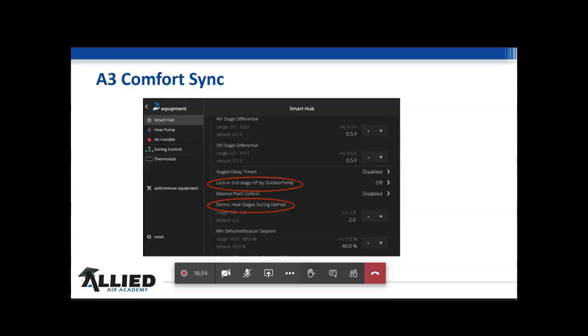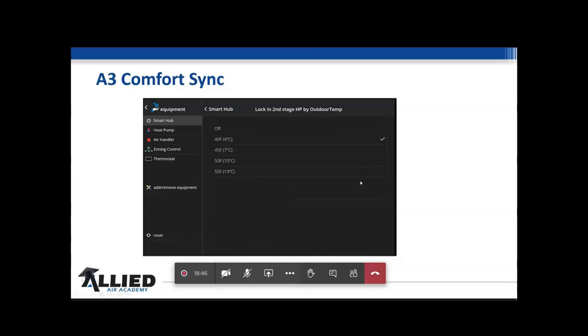So when I go here and I look at this, I'm in the smart hub, I'm not in the heat pump yet, we'll get there in a minute. These are two of the main things I want to look for. The second stage lockout, and this is what it's going to give me. You can go 40, 45, 50, 55. That's pretty important to the customers, their comfort, but depending upon when you lock that second stage in, that can also affect how many times it'll go into defrost as well too.